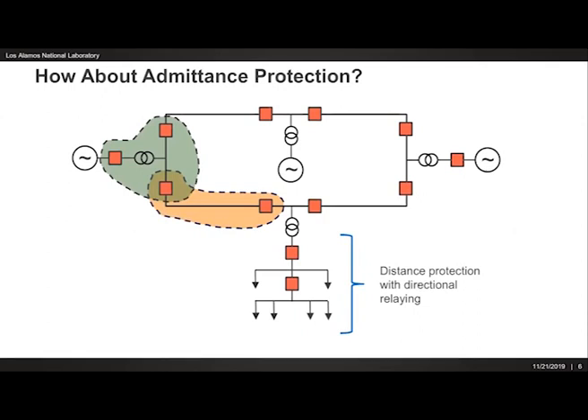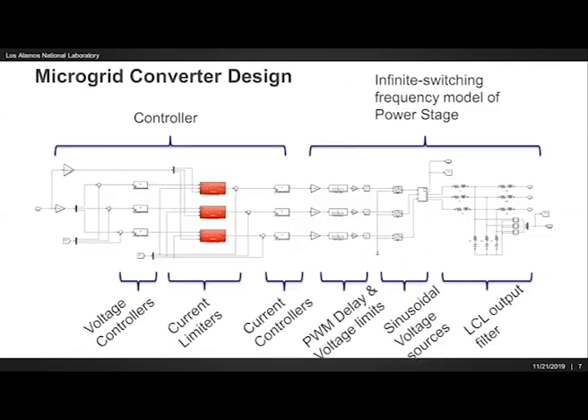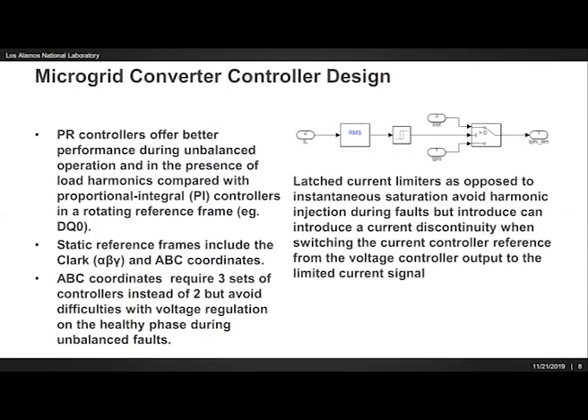So now let's look at admittance protection. The first thing to consider with admittance protection in an inverter interface microgrid scenario is that inverters behave very differently from synchronous generation. And what dominates the behavior of inverters is their control systems. Current state-of-the-art in microgrid controllers is a move away from controllers in a rotating reference frame, such as DQ0, which is commonly used in industrial motor drives, to static reference frames, either the Clarke or just the raw ABC coordinates.